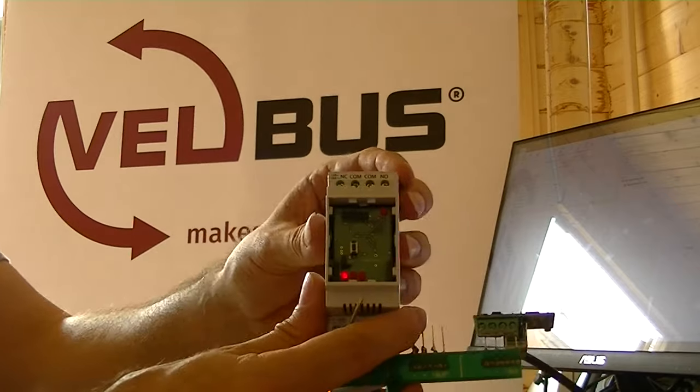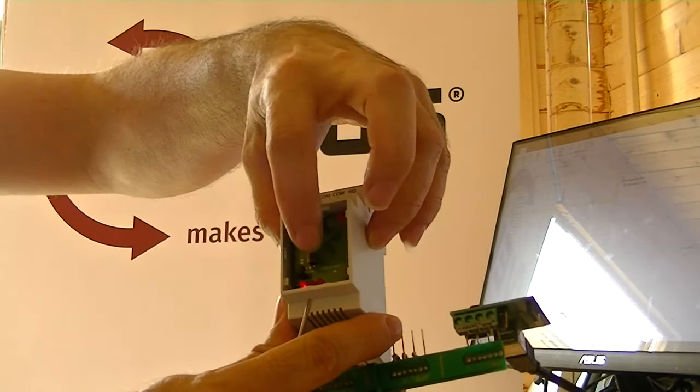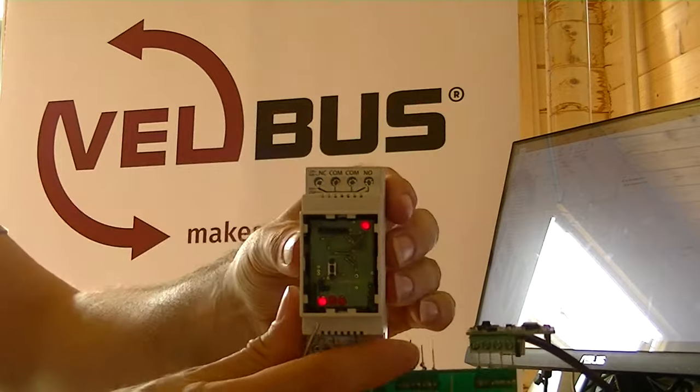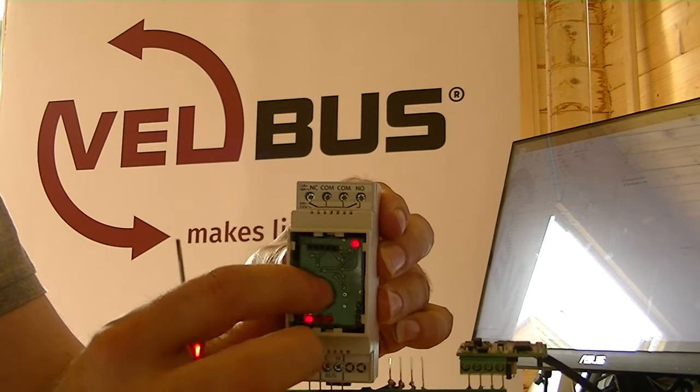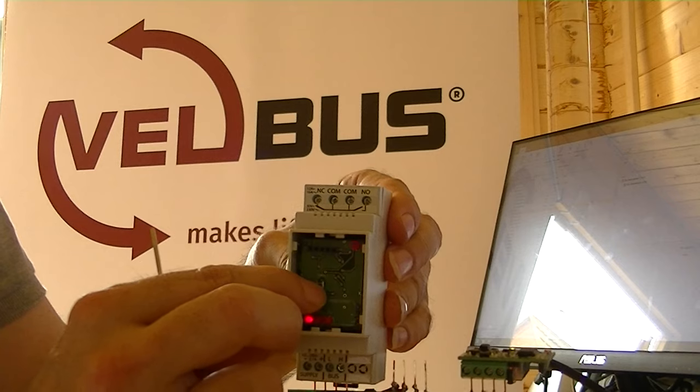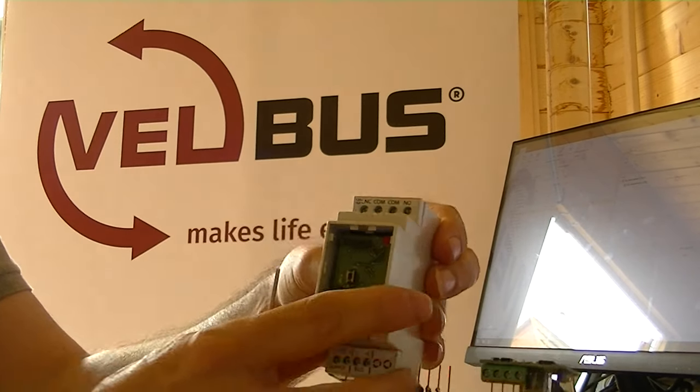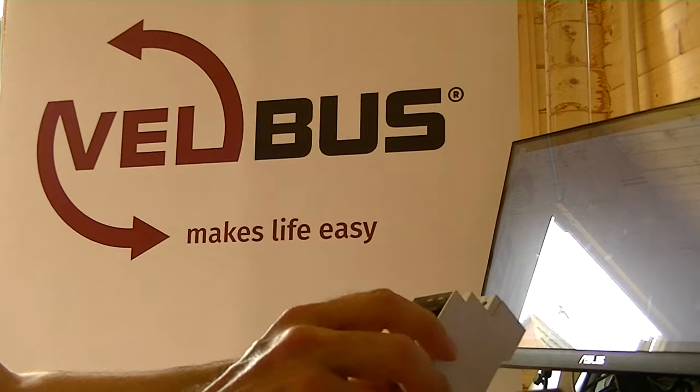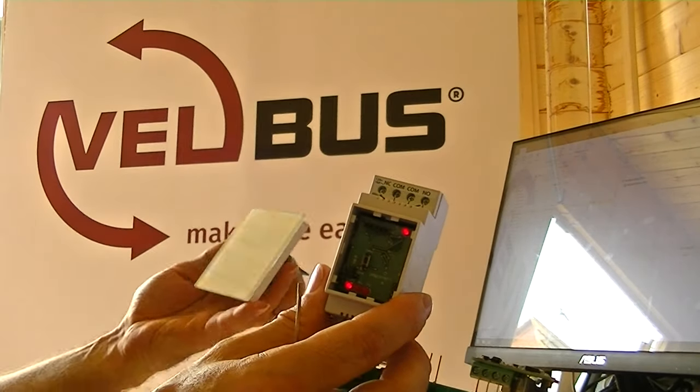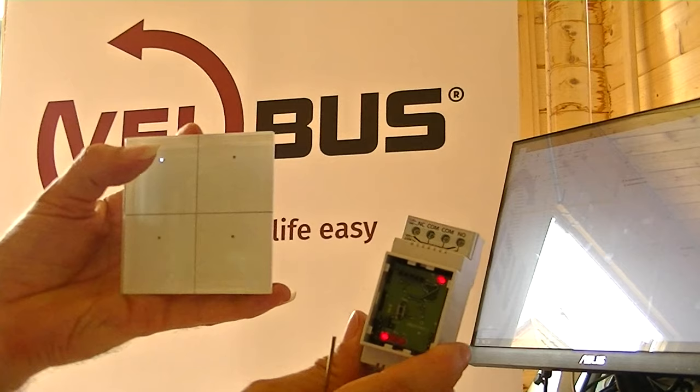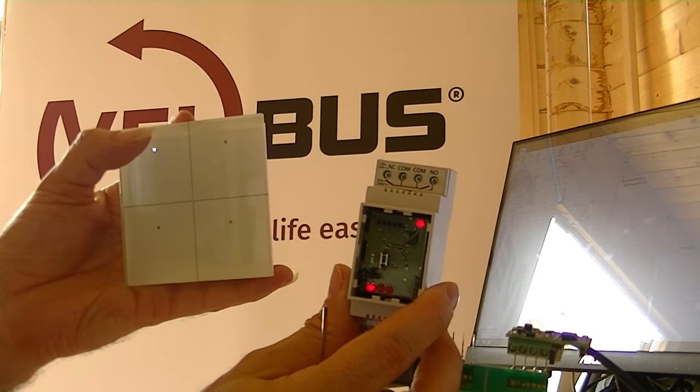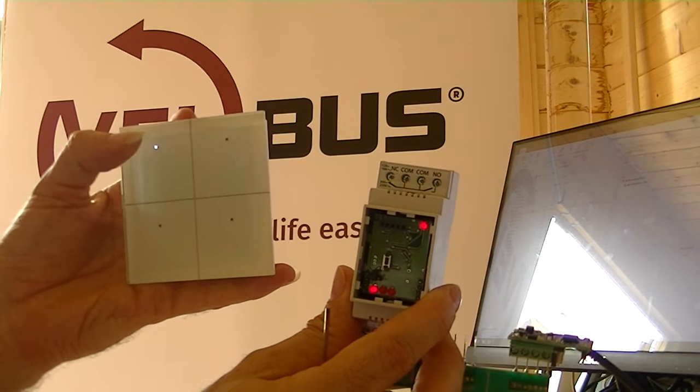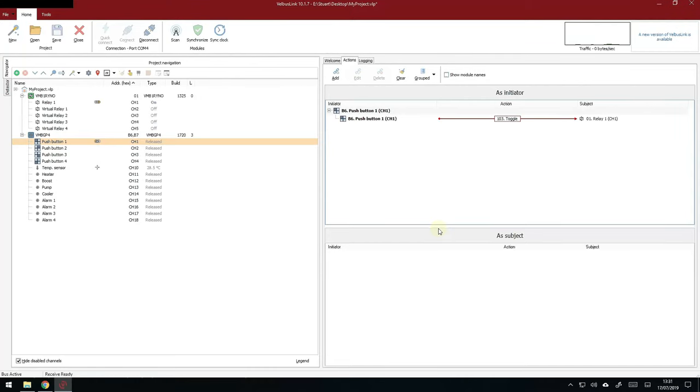So, let's have a look in the real world. There's the relay. Taking the cover off so you can see the inside. There's a little indicator light and there's a black button for physically changing the state locally. So when you're testing, you can check it's all working. You can actually check that the light you think is wired up to, it actually is. Let's pick up the glass panel and button one. Toggle off. Toggle on. You generally get the idea. It's that simple.